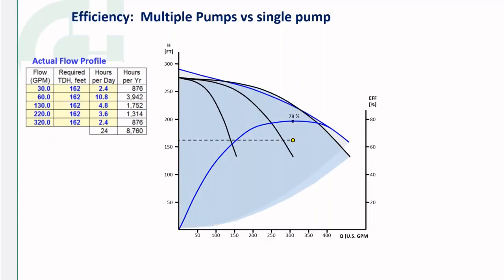So now let's take a look at a triplex system. The first black line is one pump running, and then two pumps running, and then all three pumps running at the same time, three pumps in parallel. And now here's our efficiency curve for the triplex system. Note that we max out at about 72%. So one might say, what's better, 78% or 72%?